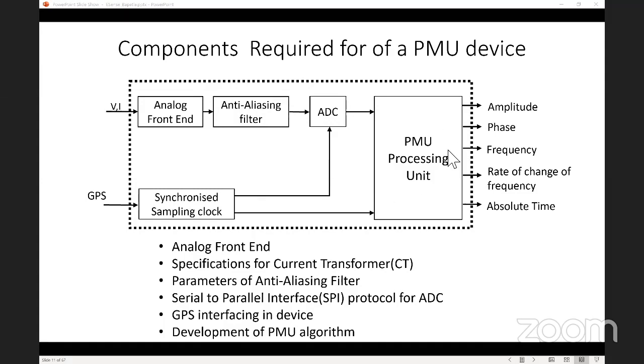Then the PMU processing algorithm - this need not be a PMU. For example, for a relaying application, you need to do a DFT and get the fundamental. After getting the fundamental, you may use a threshold based approach, or do distance protection by calculating impedance. There may be a requirement to give certain outputs - for example, from my PMU: amplitude, phase, frequency, rate of change in frequency, and absolute time.